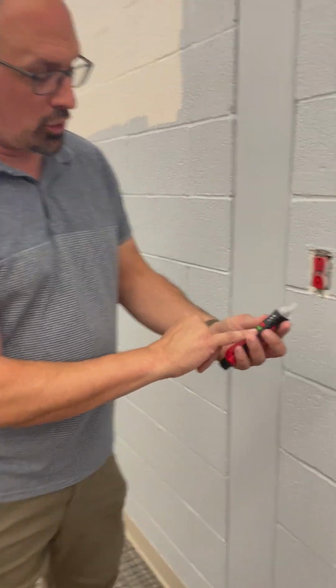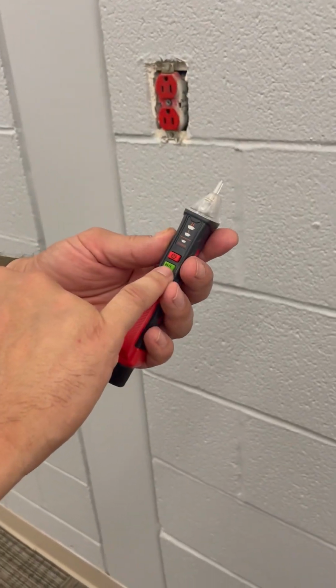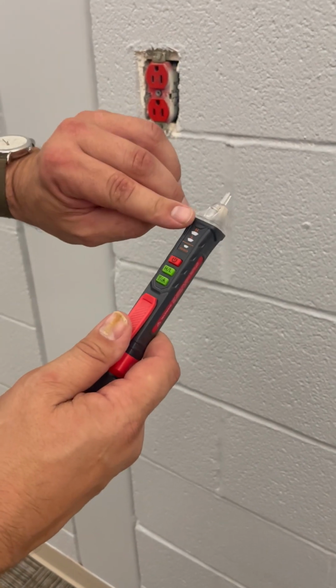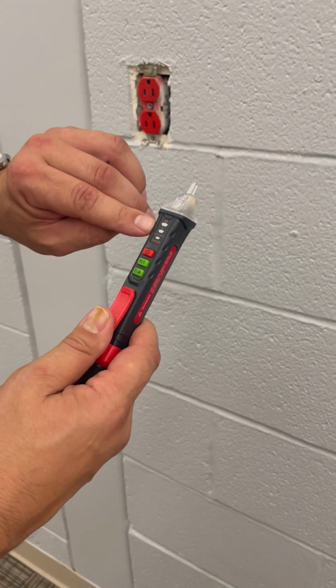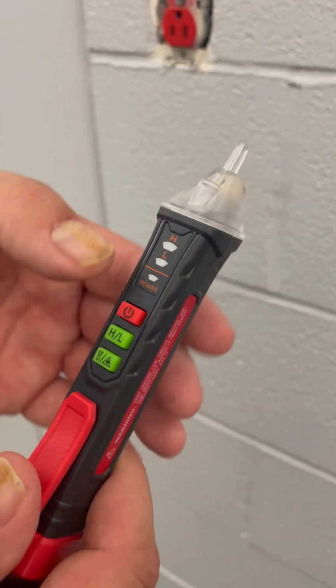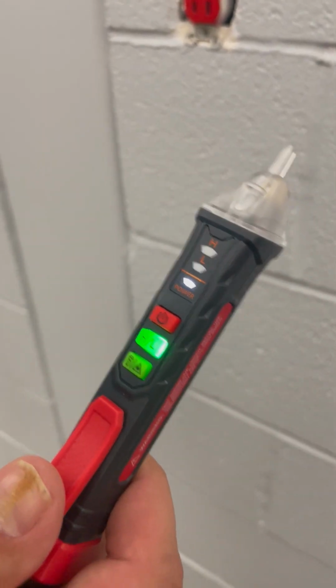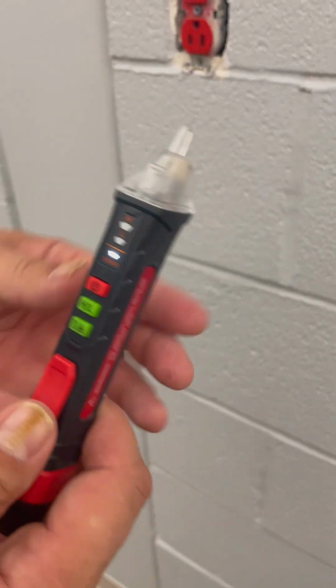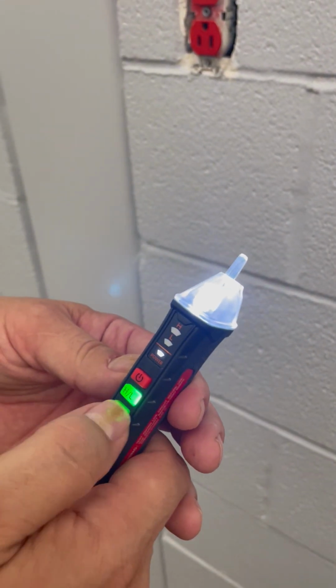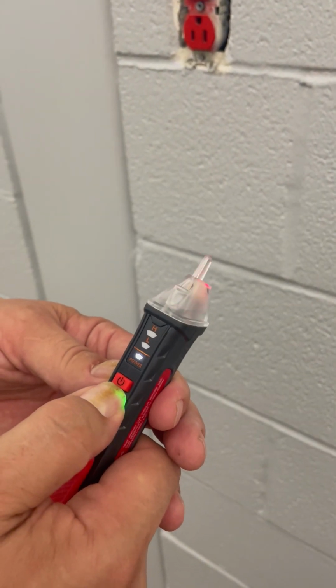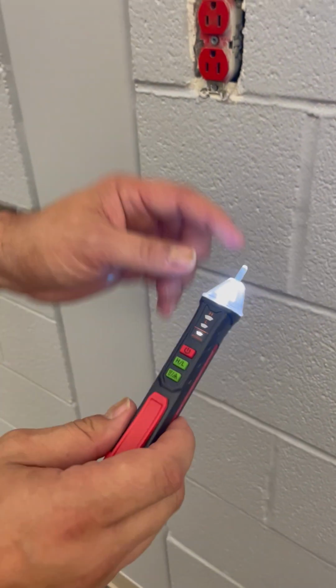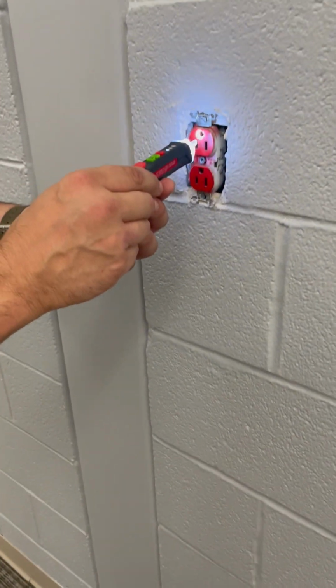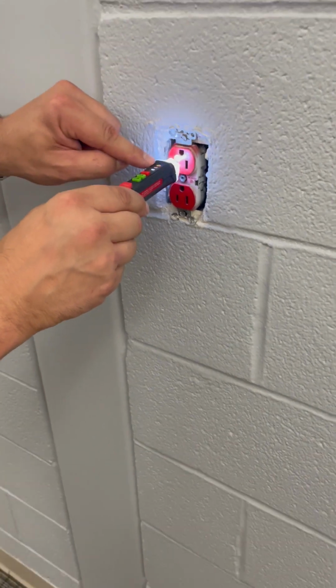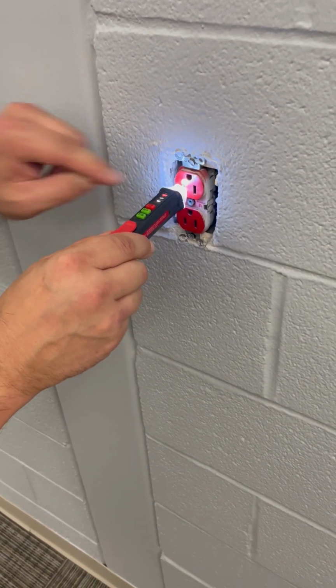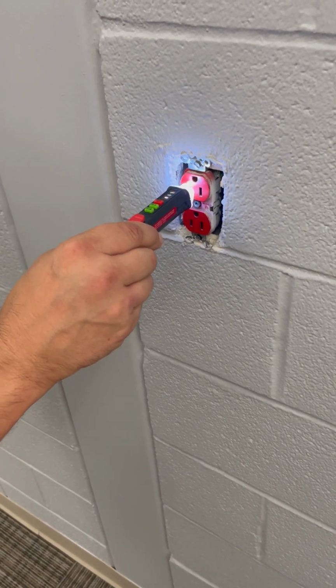This no contact tester is high-low voltage, so it's got an H and L on it, then its power button. So I hit the power button, it's on. I hit for high-low, and we'll see what it tests for here. Your light goes on. If I stick this in, it's telling me it's high voltage. That is my hot.